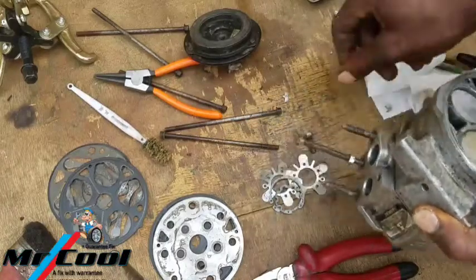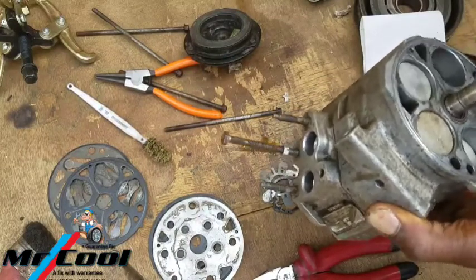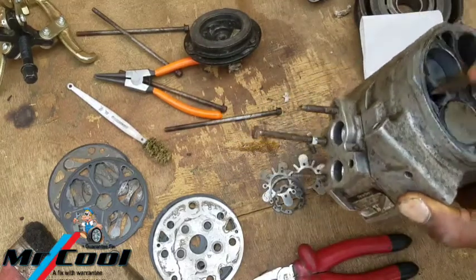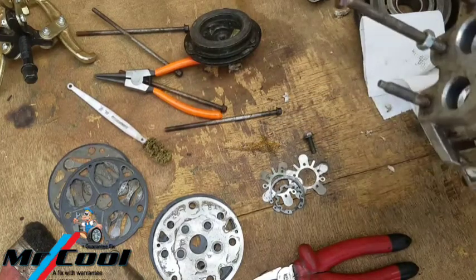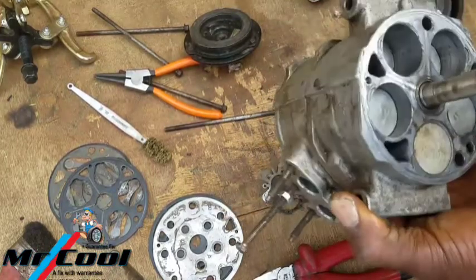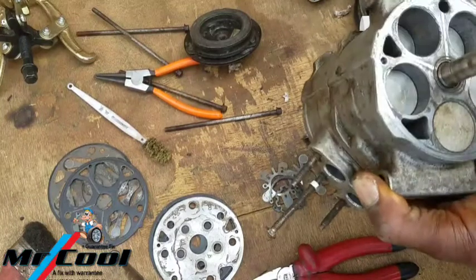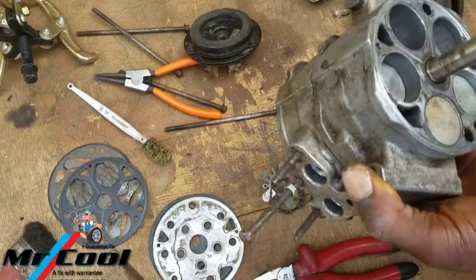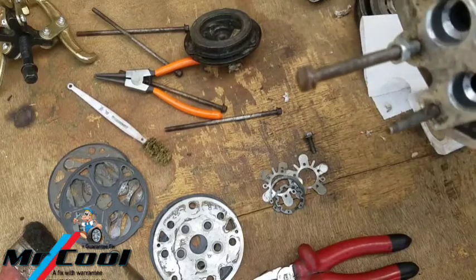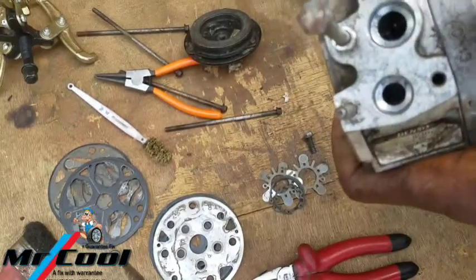I would have recommended you use some grease, either grease or something else, to lubricate it, and it's actually going to improve the system further. But I'm actually trying to think about the aftermath. What happens when it mixes with your refrigerant? What could possibly go wrong? I've seen a lot of guys do it, but I think it could even block the expansion valve. Though I don't think it's going to ruin the system, because this compressor actually needs it.